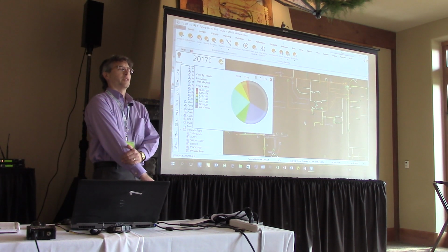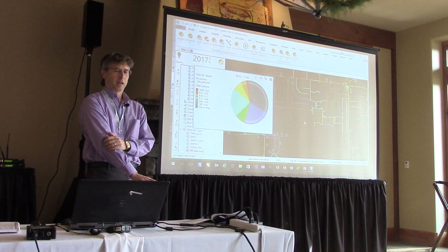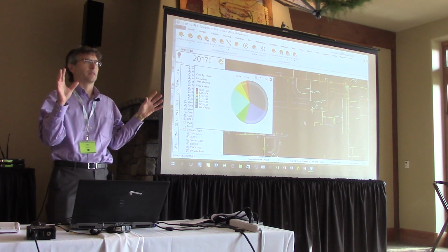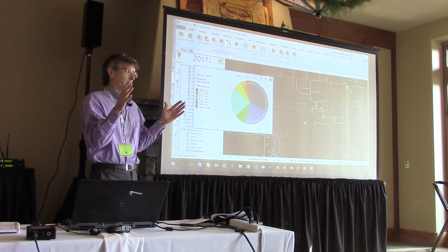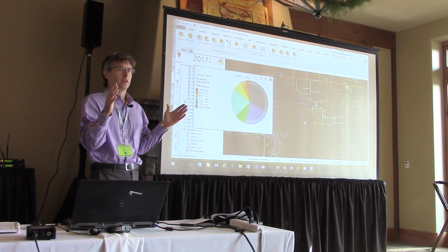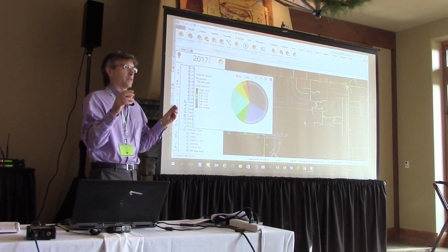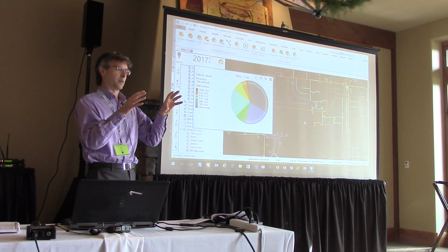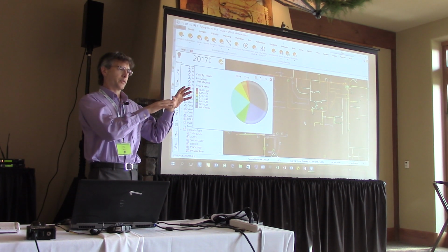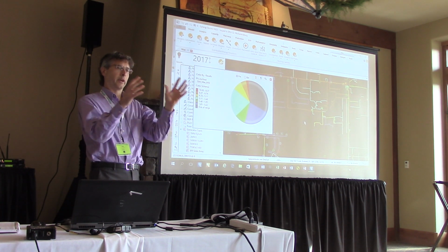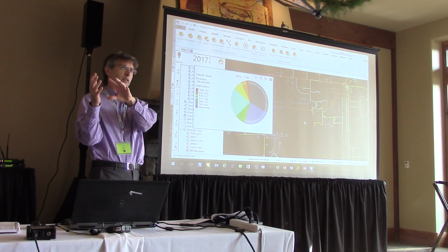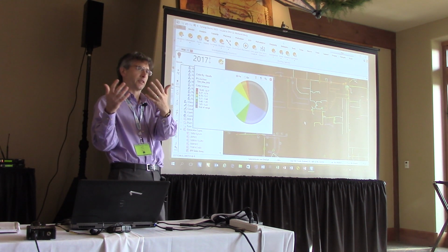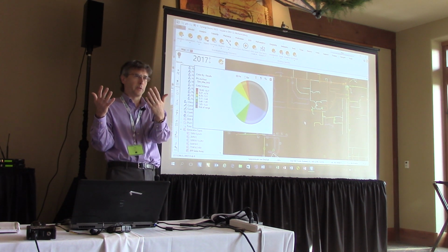One thing, and you folks are probably here, I can't remember exactly who I was talking to about it: if you've got switchable sections, there are company policies that you're never going to have more generation than you have load on a switchable section. Imagine you've got a transfer scheme and some generation over here, and the transfer scheme for some reason would transfer this generator to a section over here that has little load. If that transfer results in the generation exceeding the load, you don't want the generation to be that high.